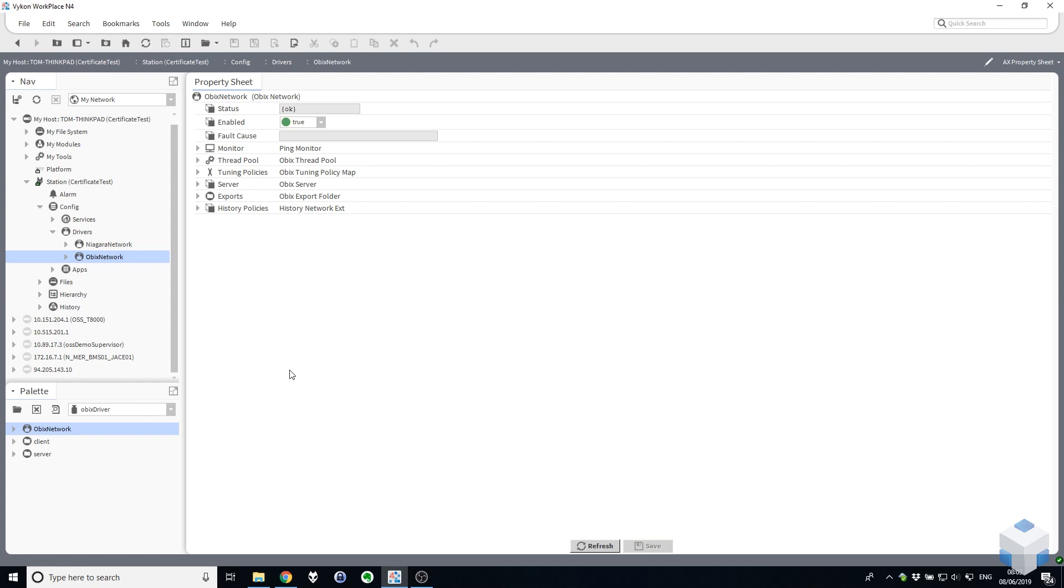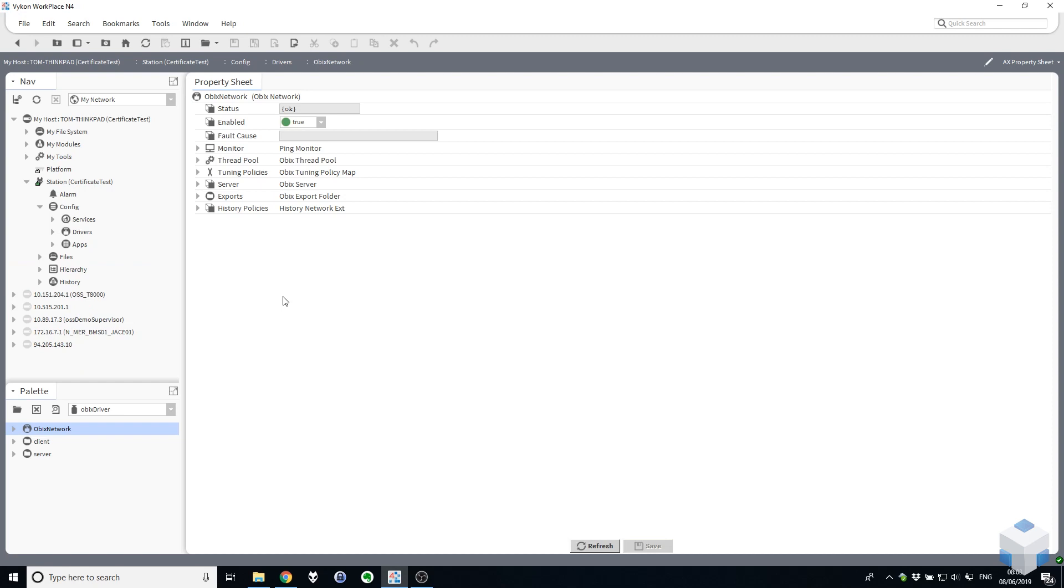There's just a couple of closing notes to add to this. The most common and important one since Niagara 4 was released is that OBIX doesn't work with HTTPS. That's an incorrect statement and the reason for it is due to the fact that Niagara ships as standard with a default self-signed certificate that it uses on the web server for HTTPS. Now, you'll know when you navigate to a Niagara station in the web browser that uses that default Tridium certificate, you get a connection error that tells you that the certificate doesn't match or it's not trusted. That's okay in a browser effectively because you can just click ignore.